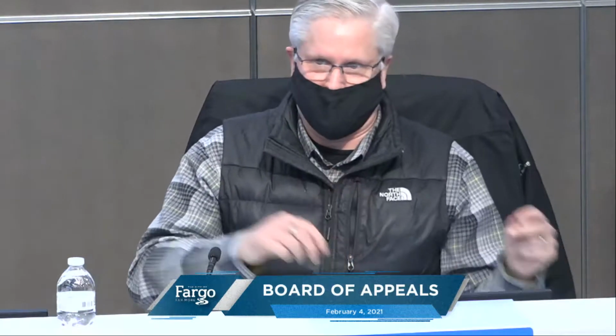If it was, we would go to 508.4 and it would clearly say that U and S2, generally, when you look at that column there, the only N for no separation requirement that's in that category is between F2, S2, and U. And if you go all the way down the line in every other single category, there's a separation requirement. So that tells me that either it's never been done, or there's a specific reason why they wouldn't have said, okay, putting a private garage inside of a public garage could happen someday. I don't think that they anticipated that with that statement.